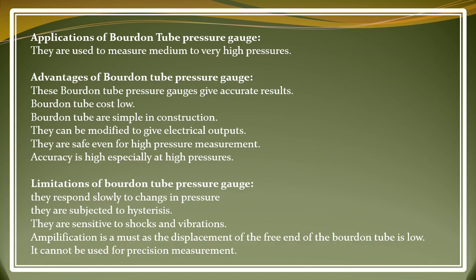So now let's talk about the Bourdon tube pressure gauge. What is the application of the Bourdon tube pressure gauge? Normally the Bourdon tube pressure gauge is used to measure medium pressure and high pressure. As we talked in our previous video, low pressure can be measured by manometers or micromanometers. There are many types of manometers. So what are the advantages of the Bourdon tube pressure gauge? The Bourdon tube pressure gauge gives an accurate result, so it is precise. The Bourdon tube cost is low. Bourdon tubes are simple in construction. They can be modified to give an electrical output.